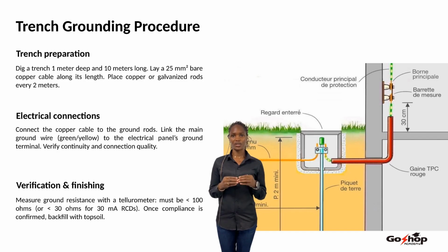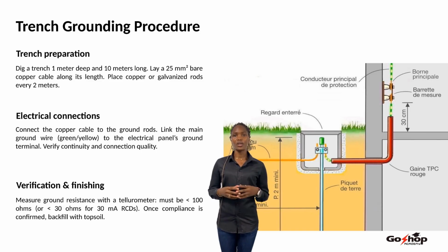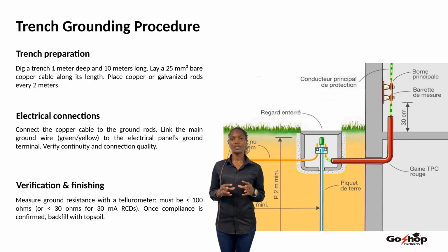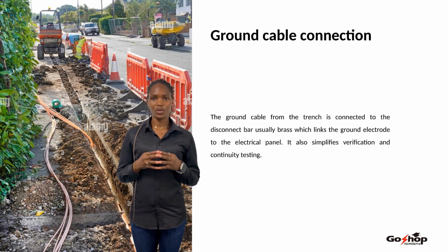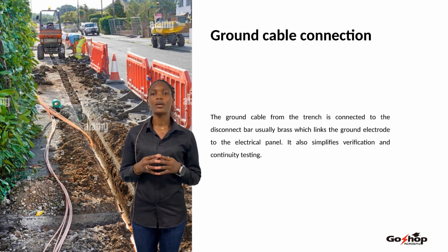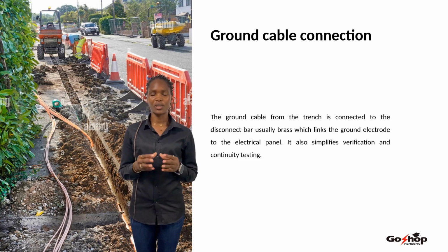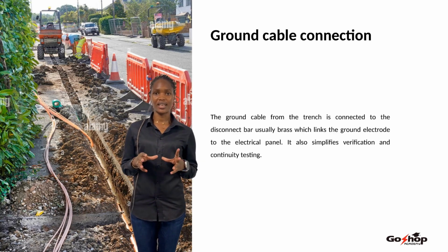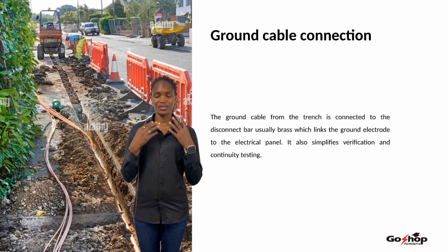For trench grounding, dig a trench 1 meter deep and 10 meters long. Lay a 25 mm² copper cable. Insert a ground rod every 2 meters and connect them to the panel. Check the connection. Then measure a resistance of 100 ohms, or 30 ohms for 30 mA RCDs, with a tellurometer before backfilling. The ground cable from the trench is connected to a disconnect bar, usually made of brass. This bar connects the ground system to the electrical panel and allows easy checks and measurements.